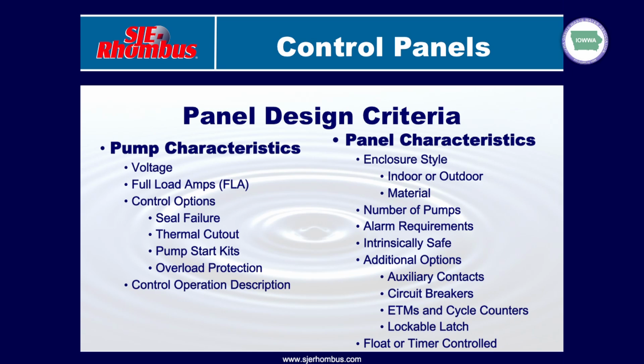And then things like a lockable latch, another option we can incorporate into the control panel. Any questions on that at this point? All right, and then we've got the ability to do either demand dose or time dose with the control panel. We can do float activation for stop, start, and alarm points of the pumps, or we can do pressure transducers. Again, there are a lot of options there so far as what we can use to actuate the pumps at a certain liquid level.